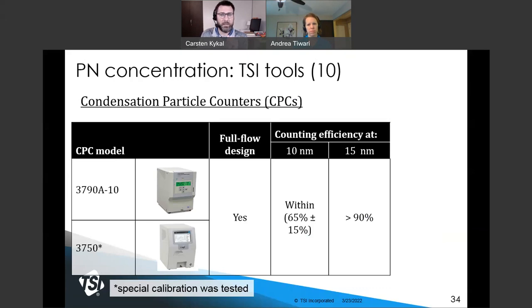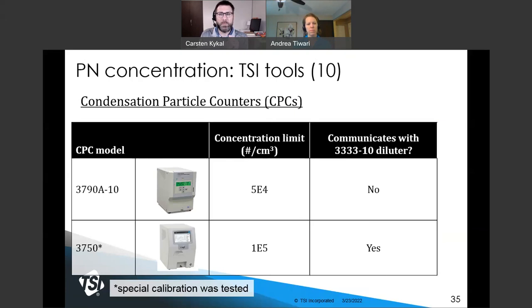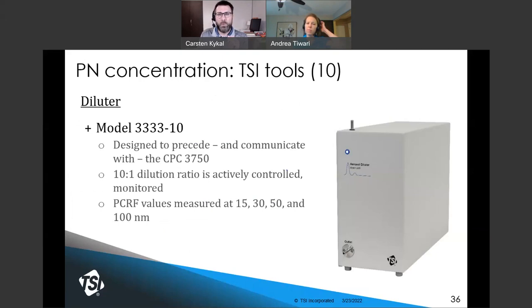The key differences between these two CPCs: the 3790A-10 has an upper concentration limit of 50,000 particles per cubic centimeter, while the newer generation can measure up to a two-fold higher concentration. The newer generation CPC can also communicate with the diluter, better enabling measurement of high concentrations of brake wear particles. The diluter is designed to work with the CPC 3750 in terms of flow rate and communications, providing a controlled 10-to-1 dilution ratio and communicating the actual ratio and relevant control parameters to the CPC. Dilution data are stored right alongside particle data, and these instruments working together can provide particle number measurements required by the PMP protocol.